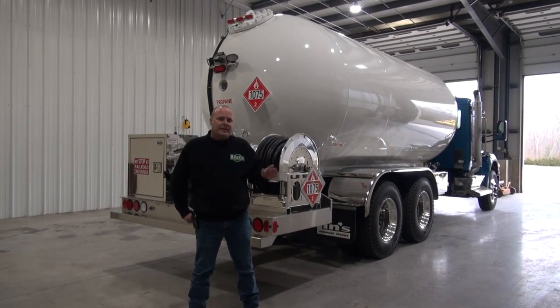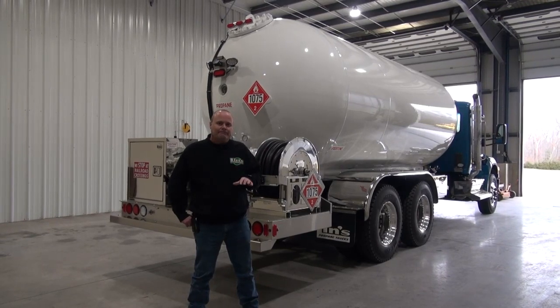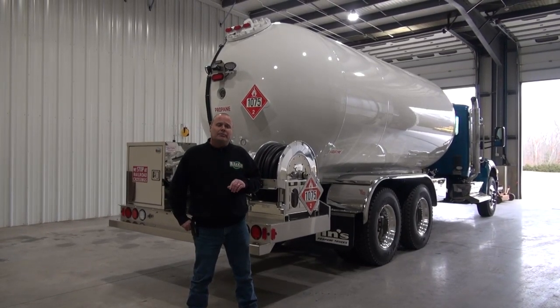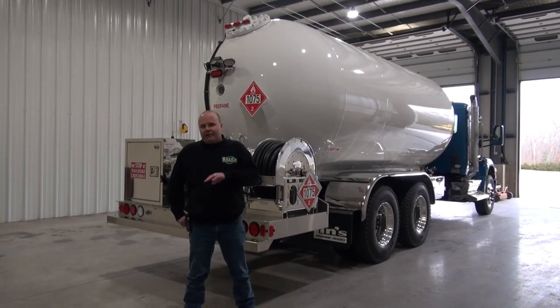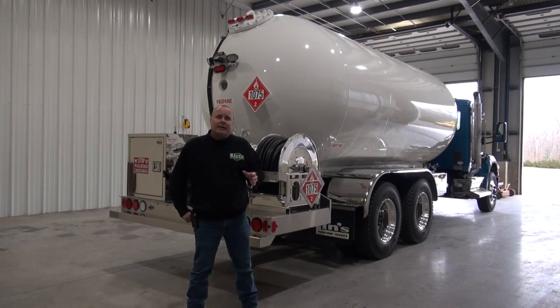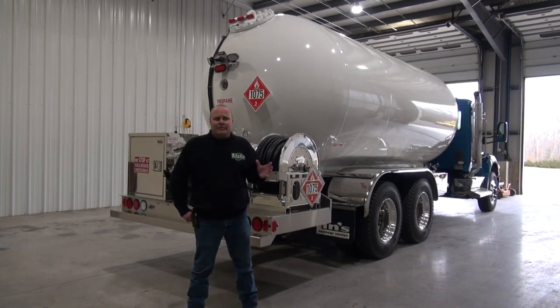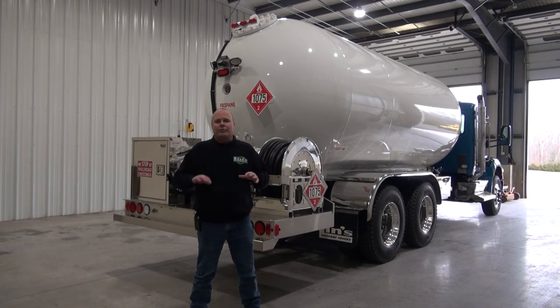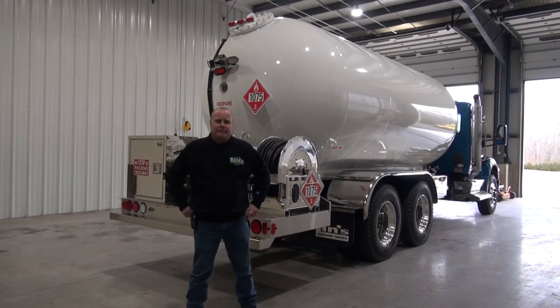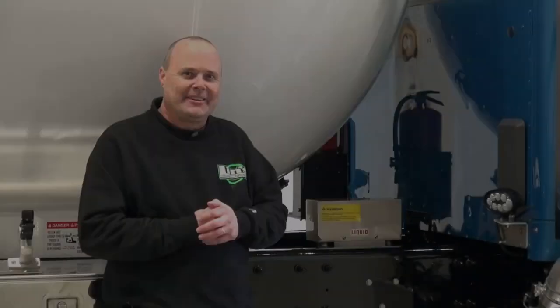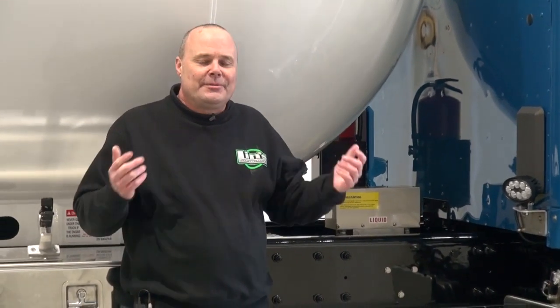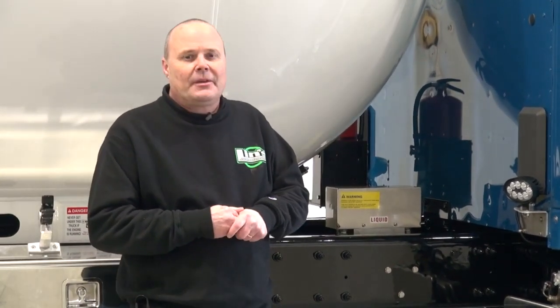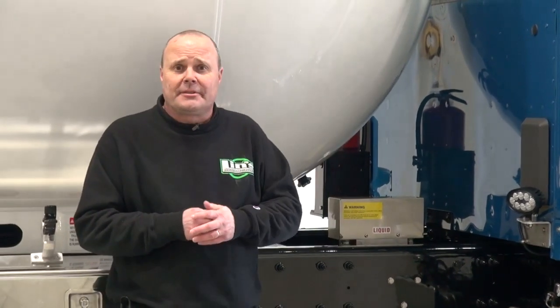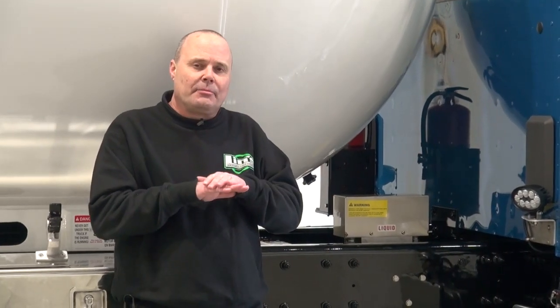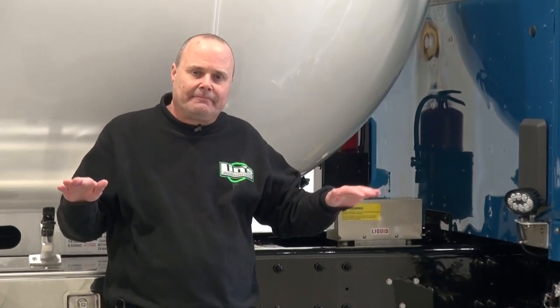So we wanted to take a few minutes today just to go over them, to explain them a little bit to you, why we use them, how they work, the different components of the heat exchanger, and also if you ever were to have a leak, what you would do to isolate it. Why do we use the Stable Flow Heat Exchanger? Well, the Stable Flow Heat Exchanger is designed to maintain the gallons per minute throughout your entire delivery.